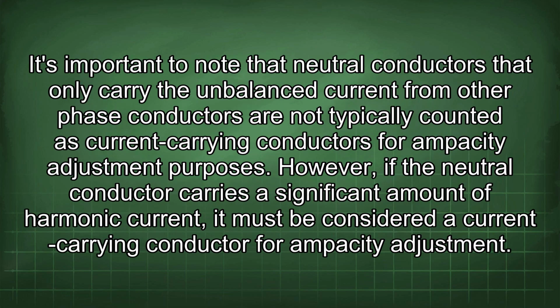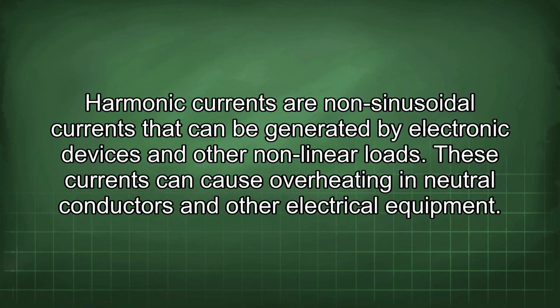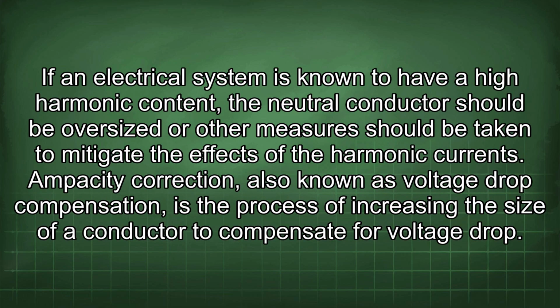It's important to note that neutral conductors that only carry the unbalanced current from other phase conductors are not typically counted as current-carrying conductors for ampacity adjustment purposes. However, if the neutral conductor carries a significant amount of harmonic current, it must be considered a current-carrying conductor for ampacity adjustment. Harmonic currents are non-sinusoidal currents that can be generated by electronic devices and other nonlinear loads. These currents can cause overheating in neutral conductors and other electrical equipment. If an electrical system is known to have a high harmonic content, the neutral conductor should be oversized or other measures should be taken to mitigate the effects of the harmonic currents.